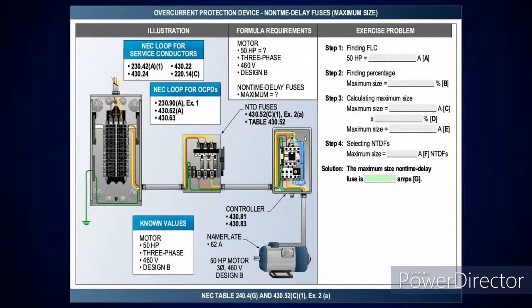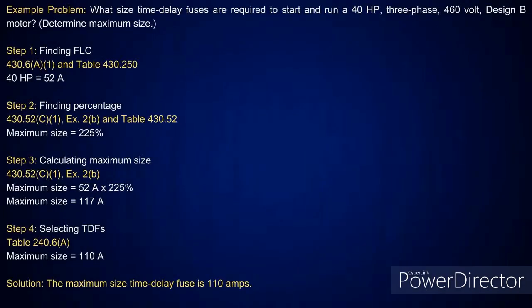Then if you look here, it's the same motor that we did earlier for the non-time delay fuse. The only thing I'm doing here, I can tell you it's 65 amps, so I'm going to take it at 400%. Then if I look at the next one, here's a time delay fuse. I'm going to come down and pick up exception 2B.